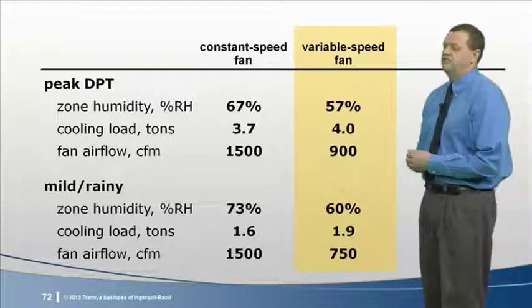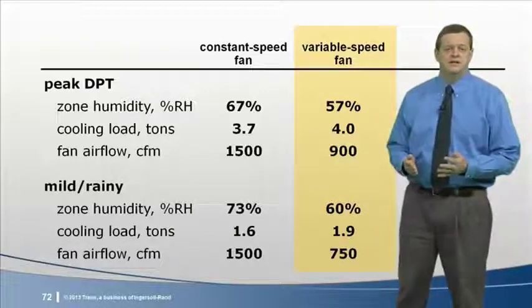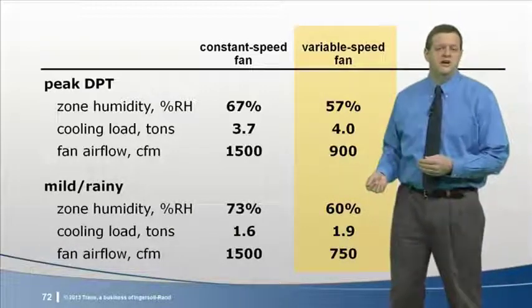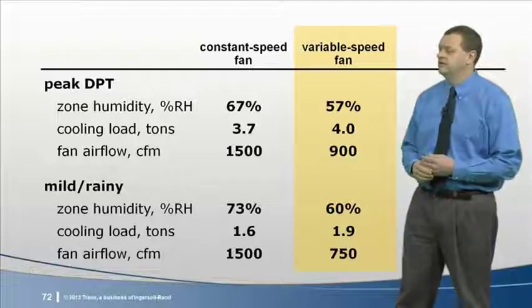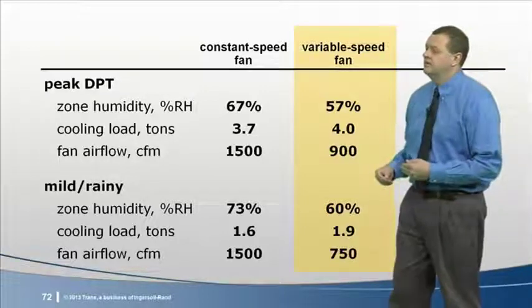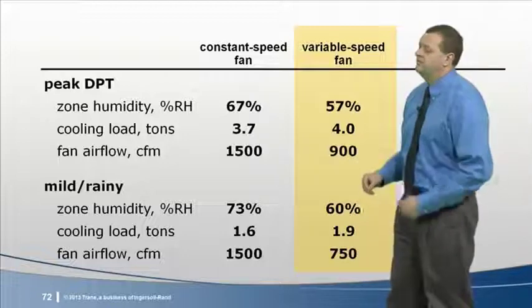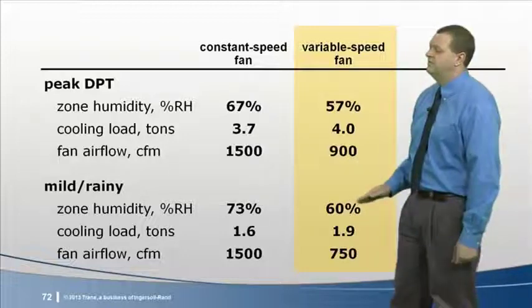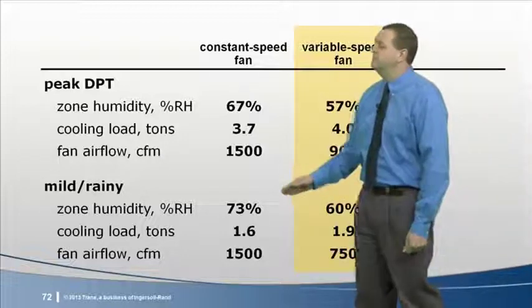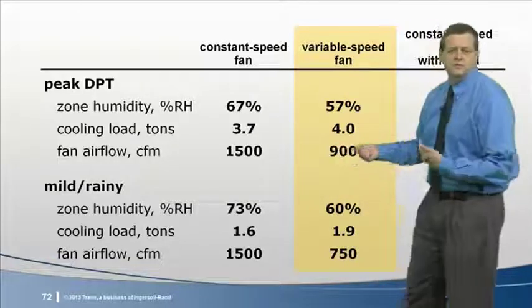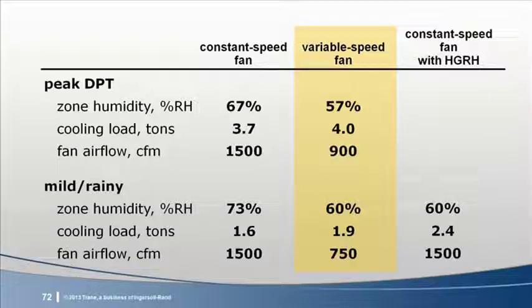Here's another challenging condition, a mild rainy day. Now I'm not going to talk through this chart, but I did include it in your handouts. Similar results here. The variable speed fan results in much better dehumidification, 60% RH compared to 73% with a constant speed fan. Now another method for improving part load dehumidification could be to add hot gas reheat.